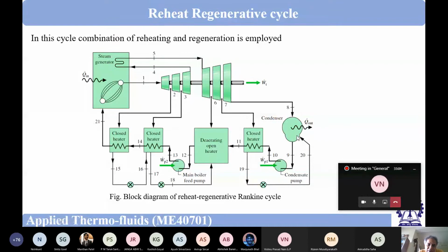So this is kind of a double penalty. Once I have condensed the steam, the cooling whatever I have done is used to cool this bleed steam, and that bleed steam is again increasing the thermal load of the condenser. So this is not a good arrangement.